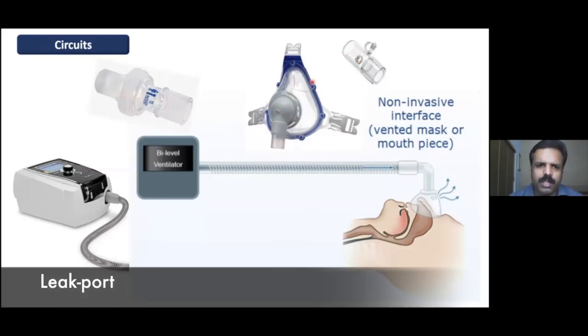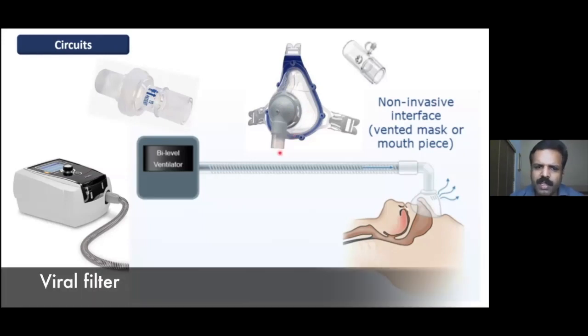There are two types of leak port. Similarly, when connecting a single-limb non-invasive ventilator to a tracheostomy tube, you must connect a leak port. In COVID settings, instead of a vented mask, we use a non-vented mask and place a viral filter followed by a leak port. Whatever gas exits is first filtered through the viral filter, then exhaled out.